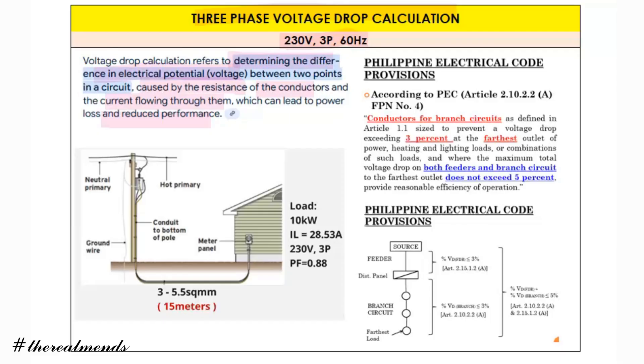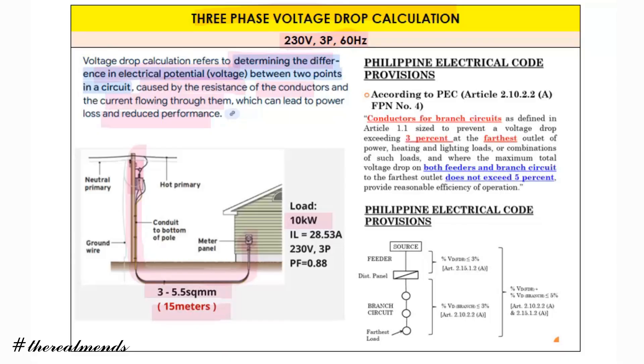So as shown in the figure, we have our utility and our load. We have assumed a 10 kilowatts load, and the length from the transformer — a step-down transformer — is 15 meters. The conductor used is 3 x 5.5 square mm. We have PEC provisions Article 2.10.2.2 (A).